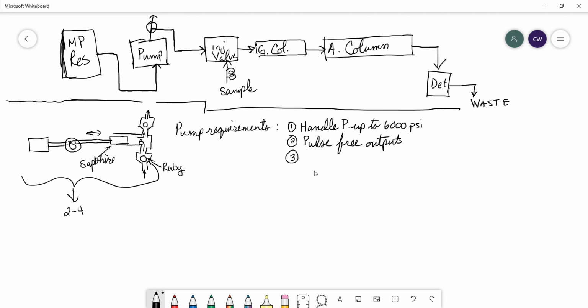They need to be able to handle flow rates from 0.1 mils per minute to about 10 mils per minute. Now, certain very narrow bore pumps cannot handle this high end of flow, and they can go much lower than 0.1 mils per minute. But most general HPLC pumps are in this region where they can handle 100 microliters a minute to 10 mils per minute reproducibly. Reproducibly is the key.